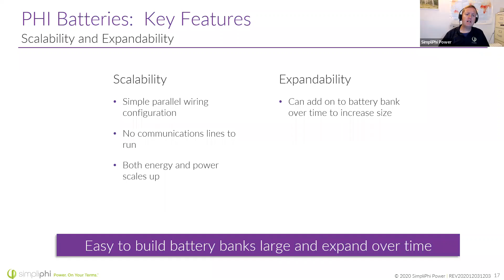Expandable, what I mean by that is that you can come back to an existing system and add batteries to that system. A lot of people ask me, well Dan, how long can you add to the system after it's been installed? Really, the good answer is 2 years, 3 years at the most. You can come back, add existing batteries, make sure that any batteries you're adding to an existing system have the voltages pretty close, within 1 volt at 48 volts. That way, you're not going to get a lot of current flow from the older or the newer batteries to each other. Also, if you do go to expand a system, the programming might need to be changed just a little bit.